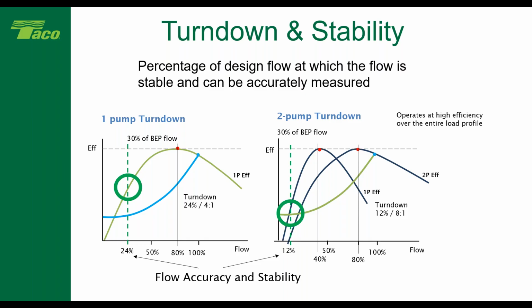Whereas if I put 2 pumps in, now I go to an 8-to-1 turn down. Okay, so I'm doubling my turn down capability, which means I can handle a much lower flow, because my 30% of BEP flow doesn't change, but it's 30% of BEP flow of one pump, not the system. So now I'm gaining even better efficiency over that entire load profile by having more turn down capability, as well as the accuracy and everything else that we need.